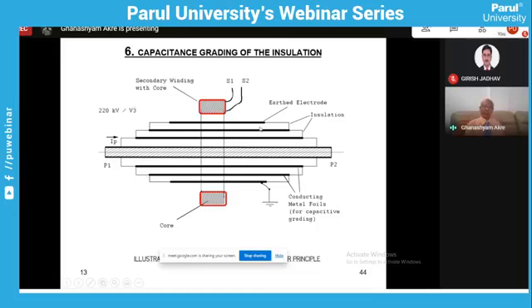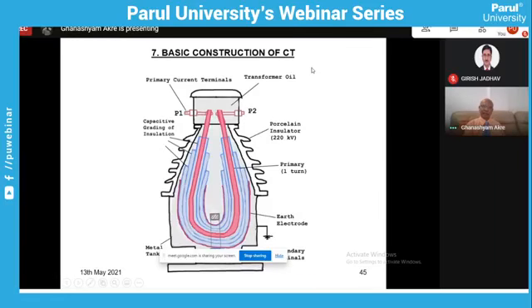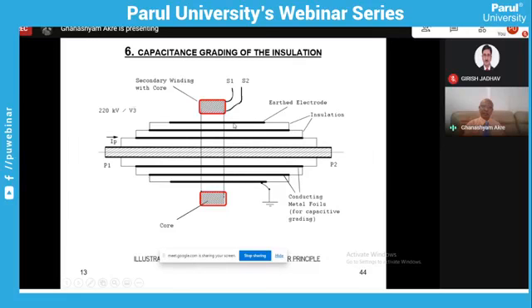Otherwise, what happens if you do not put these capacitors? Then the insulation very near to the primary, which has a lesser diameter than the earth potential at the top, suppose a 5 millimeter section of the paper here, will have a voltage gradient of nearly 130 to 150 volts per mil. So this paper will share the voltage in such a way that the first layer will have a very high stress of 150, while the same insulation at the higher level, at the higher diameter, may have only 80 to 90 volts per mil. So you can see the difference between these two. The same paper is sharing at 80 volts and 150 volts.